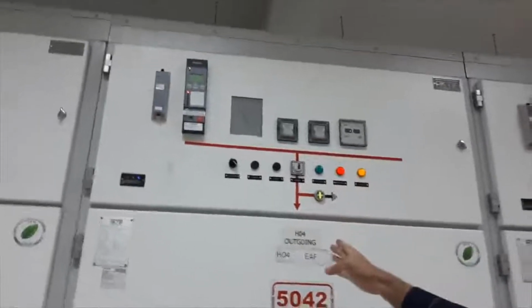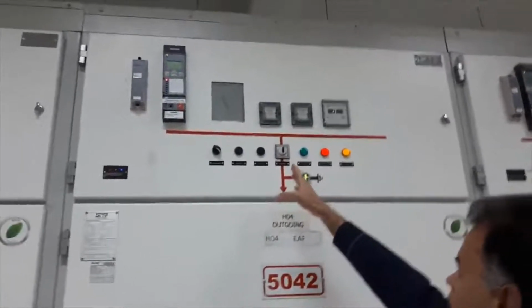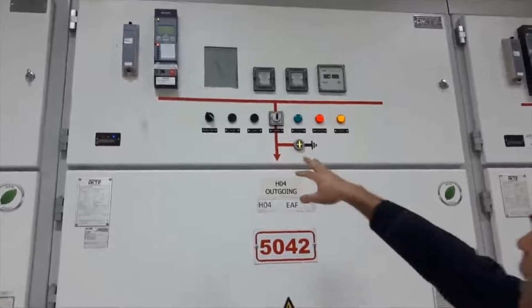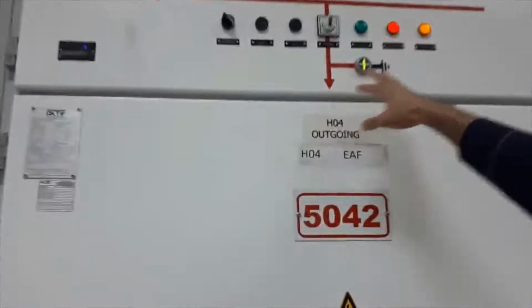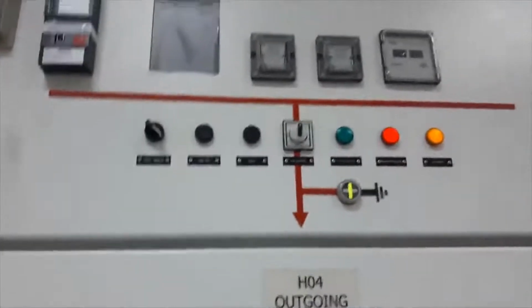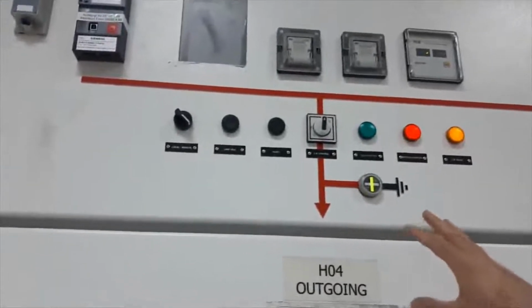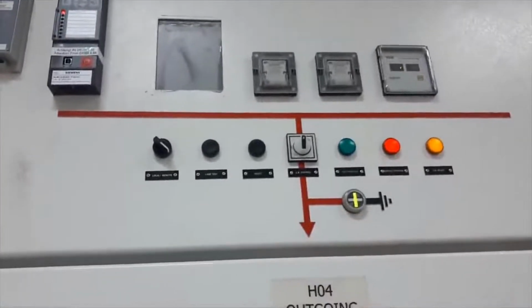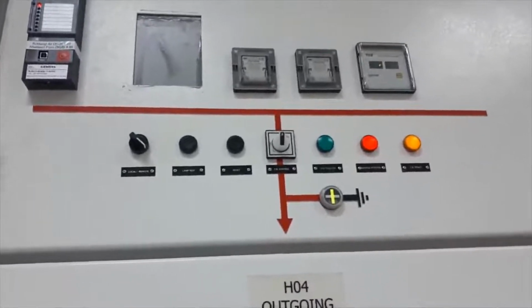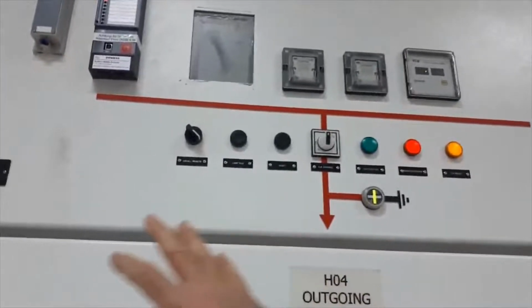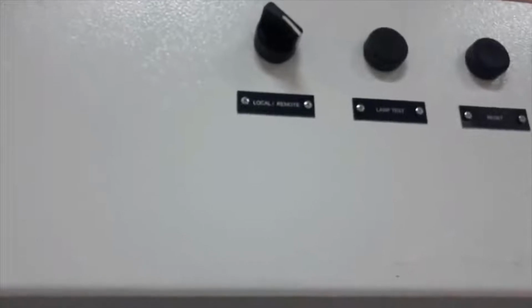Now, because it's aligned with our output, the breaker is closed. This is the semaphore that is aligned with the earth path, indicating that the earth is disconnected, and when the earth is reconnected, the semaphore will be aligned with the earth disconnector. This, as I said, represents the voltage, which indicates that we have voltage at the output. You can see the local remote switch by which we can execute commands remotely or locally.